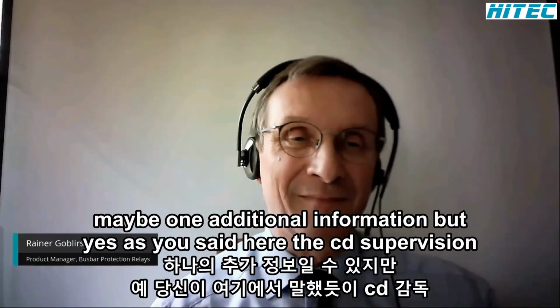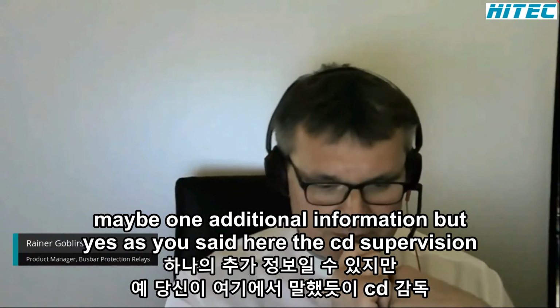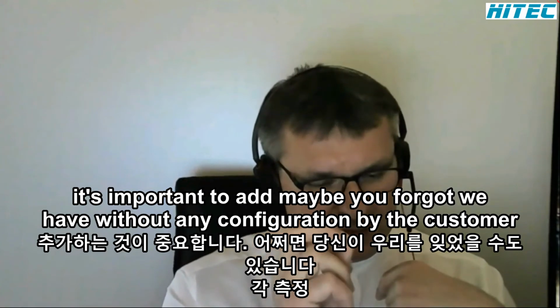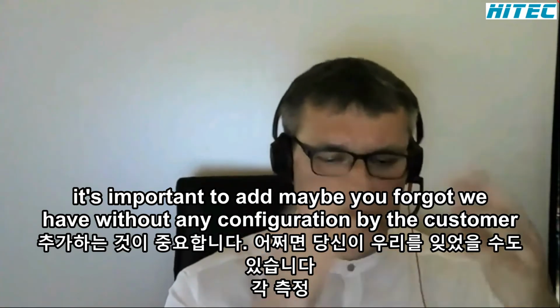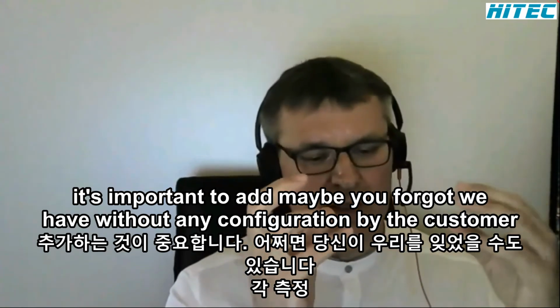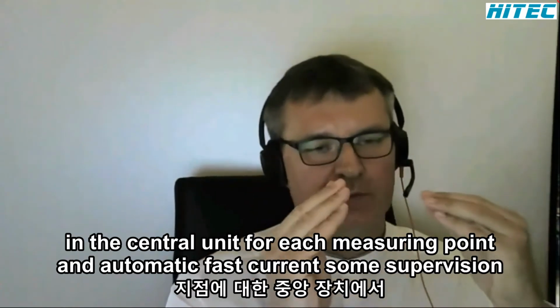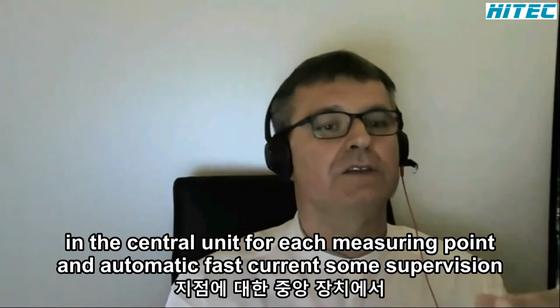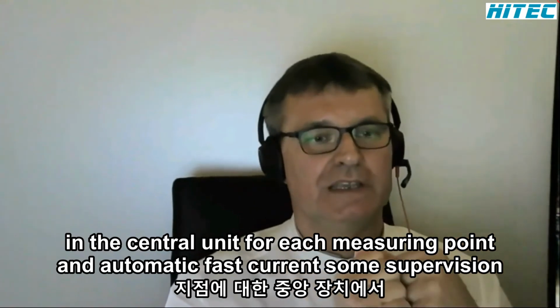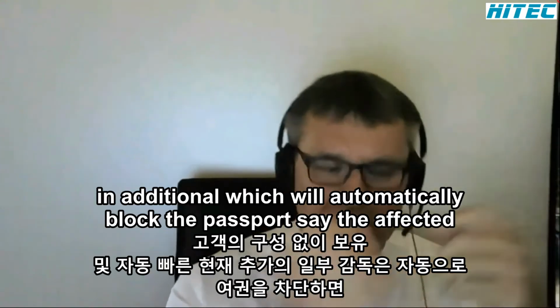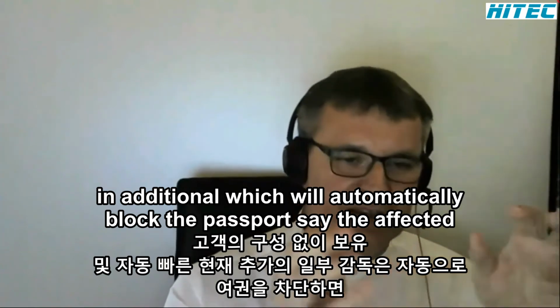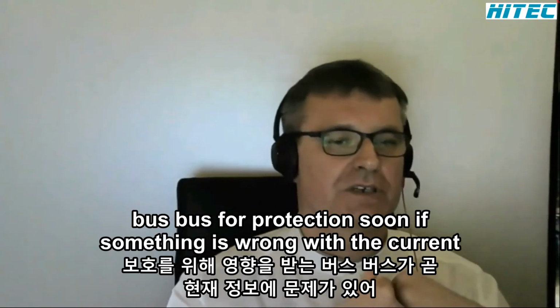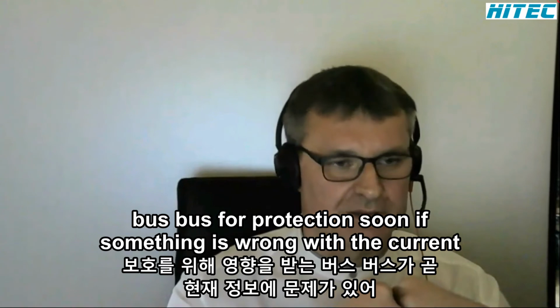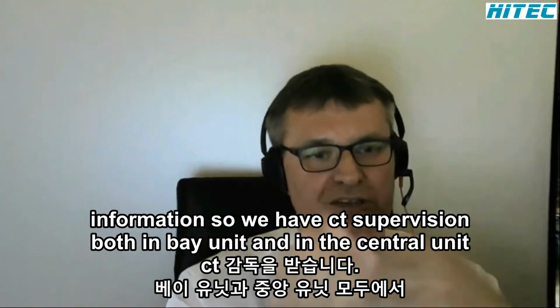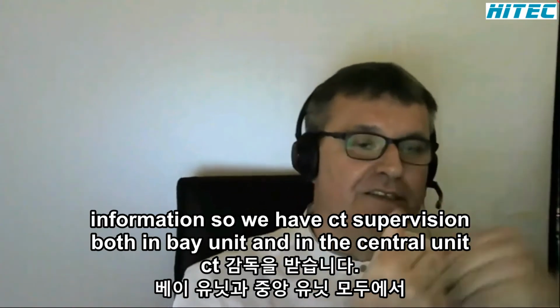Maybe one additional piece of information, Matthias. As you said, the CT supervision is important to add. Without any configuration by the customer, in the central unit for each measuring point, we have an automatic fast current sum supervision in addition, which will automatically block the affected busbar protection zones if something is wrong with the current information. So we have CT supervision both in the bay unit and in the central unit.